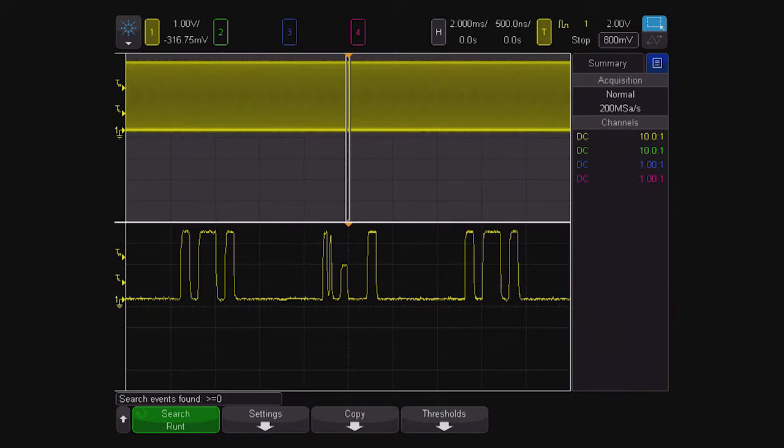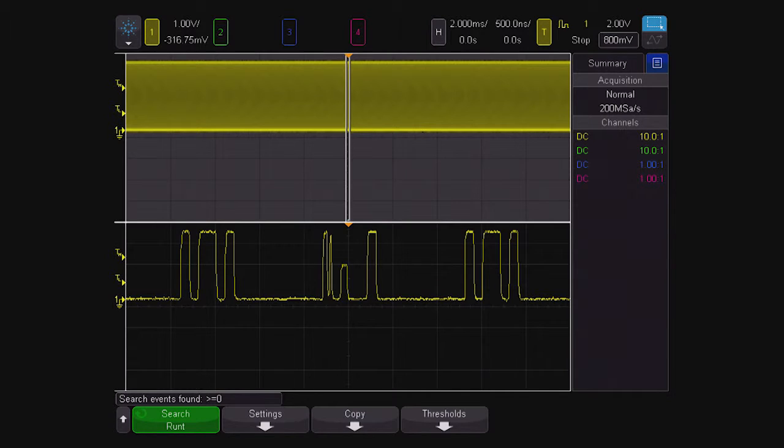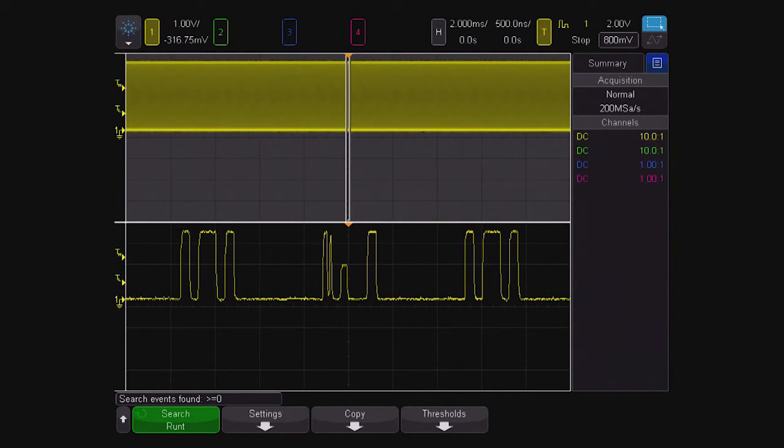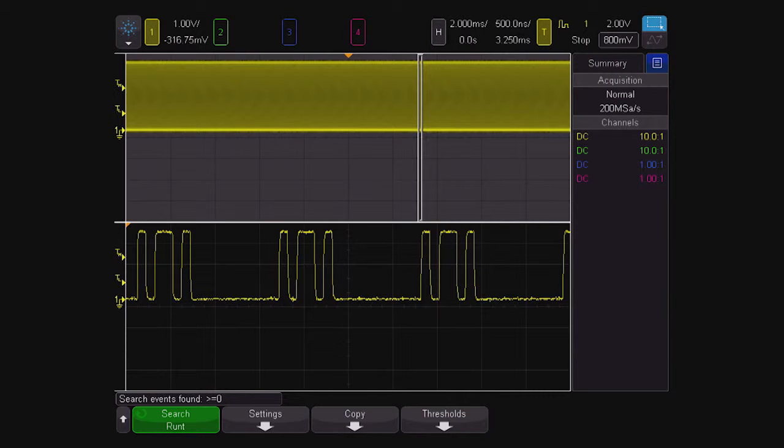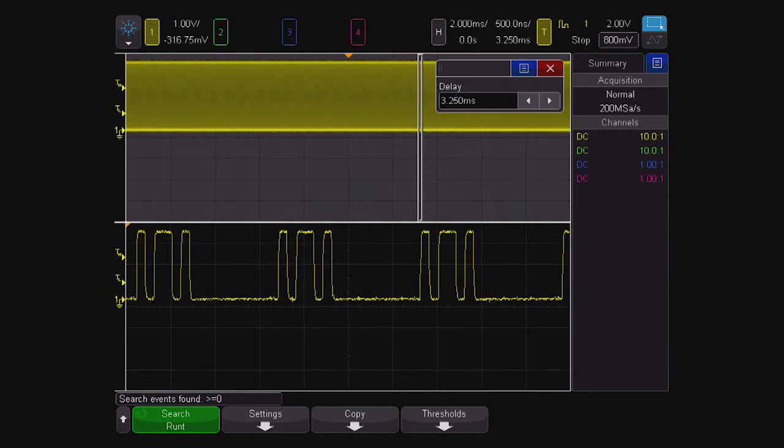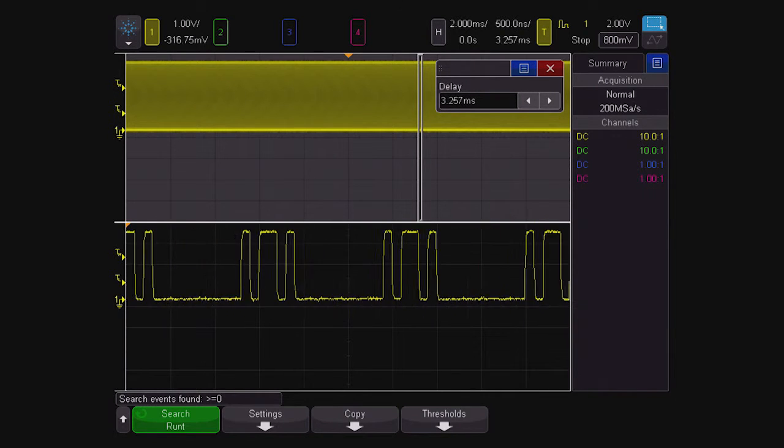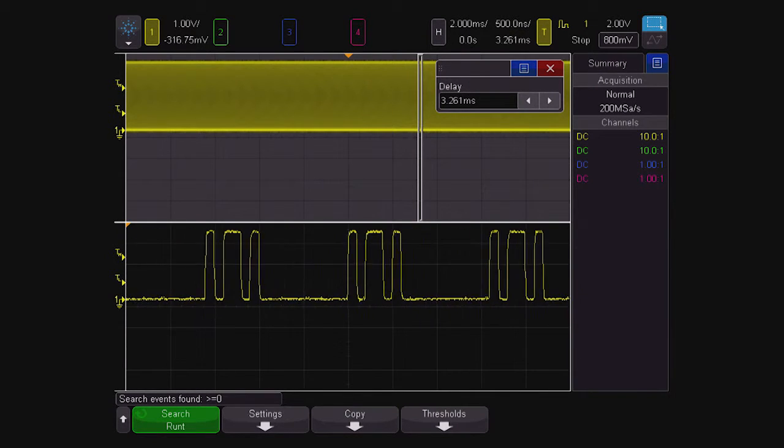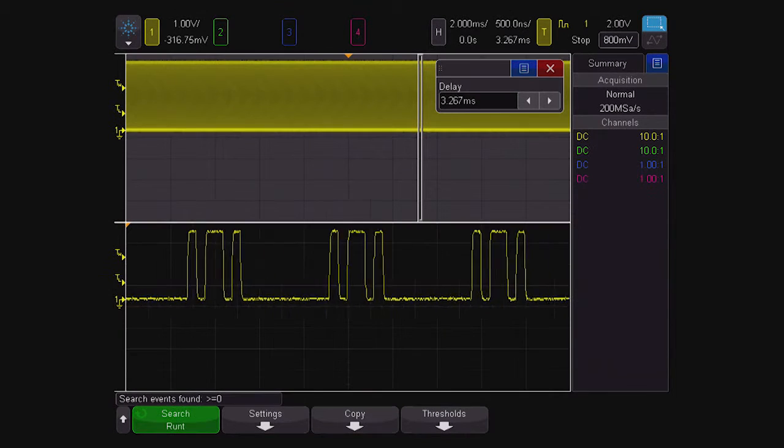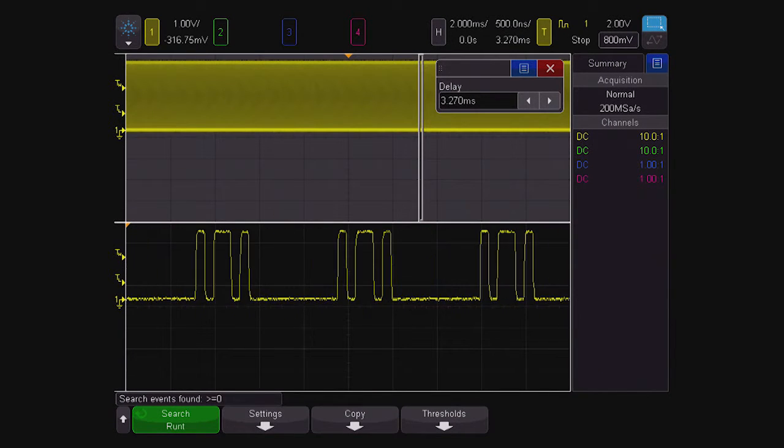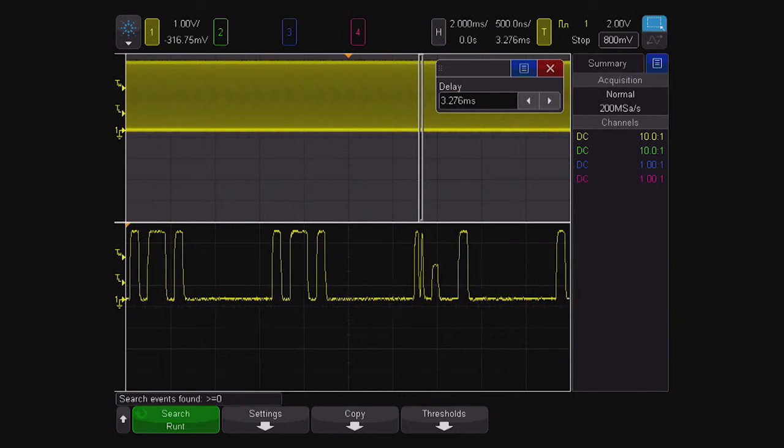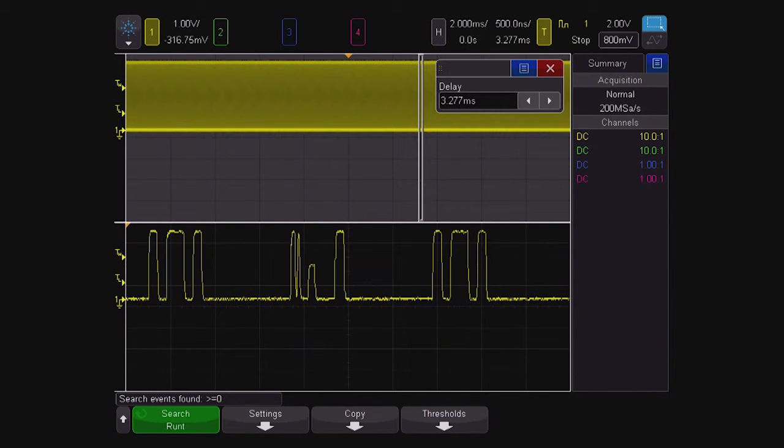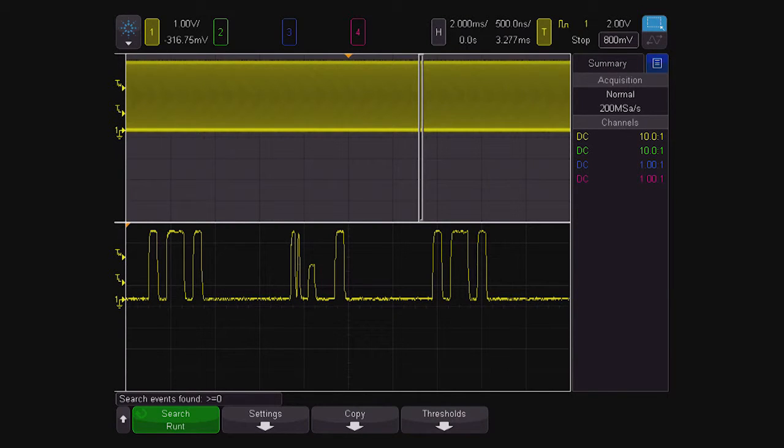We can see that the instrument found greater than or equal to zero runts in the total 20 ms captured waveform. The user manual states that the greater than symbol indicates that the measurement may not be reliable. It's curious that the Agilent oscilloscope maybe found zero or more runts, even though the scope triggered on a runt. Recall that the Tektronix MSO5204 found seven runts spaced about 3.25 ms apart through the whole record. If you manually search through the Agilent record at 3.25 ms spacings, you can find the other runts that the Tektronix MSO5204 found automatically. Not reliably finding all the runts seems like a serious problem if you need to depend on your oscilloscope to show the true characteristics of your signal.